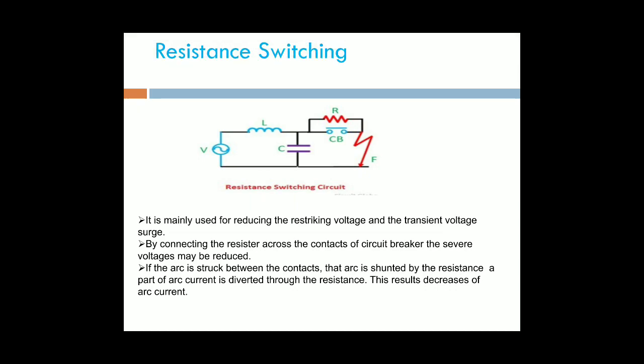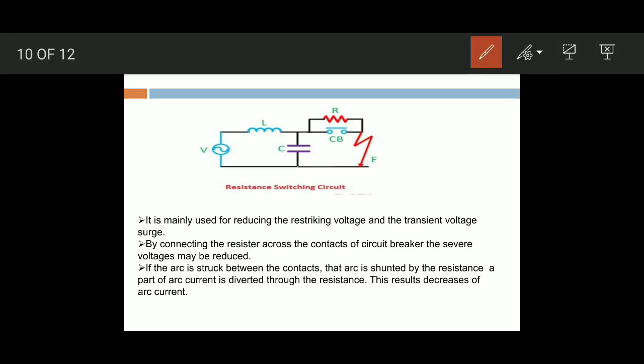It is mainly used for reducing the restriking voltage and transient voltage surges. A fixed resistance is connected in parallel to the circuit breaker, which is known as resistance switching. That resistance is connected across the contacts of the circuit breaker. By connecting the resistance across the contacts of the circuit breaker, severe voltages may be reduced. By using this resistor, the severe voltages may be reduced.